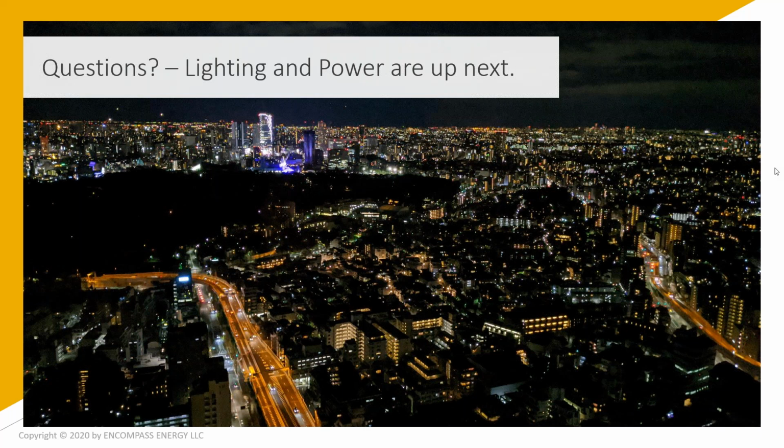For the residential, the application requirement is different. Is the zoning as one zone per dwelling unit accurate in case of residential? This is asked by Pallavi Ballamudi. Generally, it is acceptable. Like I said, there are variations in that. If you have a bunch of dwelling units that are facing the same orientation that are roughly the same size, you can group them all together in the model. But generally you're going to have one per unit.